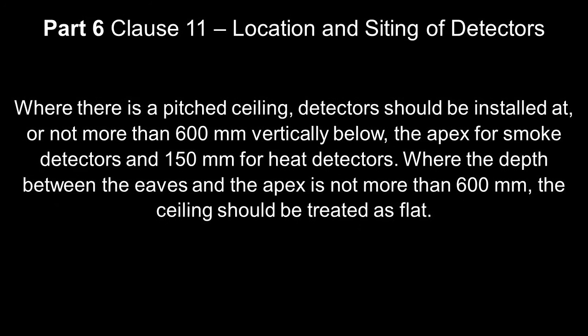I think that kind of makes sense. Hopefully it does for you. Where there is a pitched ceiling, detectors should be installed at or not more than 600mm vertically below the apex for smoke detectors, or 150mm for heat detectors. It's pretty much the same thing, but this is saying they should be installed at or not more than. It's a bit of a weird wording, if you ask me.